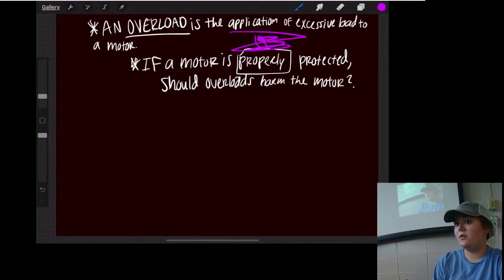Should it harm the motor? No, because you're going to have relays in place - literally called overload relays. So should you always put an overload protection on the motor? I would think you need some type of protection on that motor.